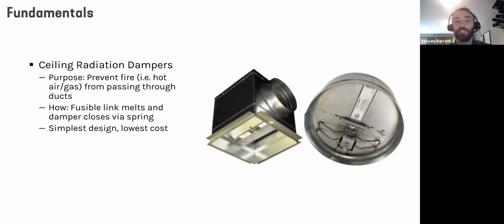Now, a ceiling radiation damper is kind of a special type of fire damper. It operates on the same principle of a fusible link melting and the damper closing. But these are pretty specific. You'll typically only see these in fire-rated corridor ceilings.